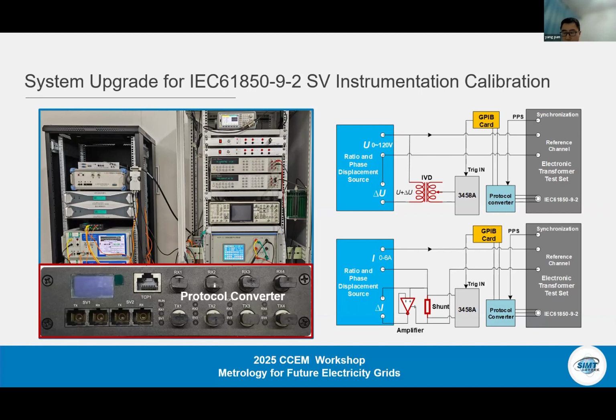The protocol converter's function is to input and output data conforming to either the IEC 61850 protocol or the FT3 format, identifying its encoding method and baud rate, and convert it to TCP format for transmission to the computer. Additionally, the protocol converter can function as a synchronization signal generator, producing PPS or IRIG-B format synchronization signals, or receive input from these two synchronization signal formats. Through the use of the GPIB data acquisition card and the protocol converter, continuous and real-time packet reception and transmission can be performed on electronic instrument transformers and electronic instrument transformer calibrators, enabling data comparison within that second.